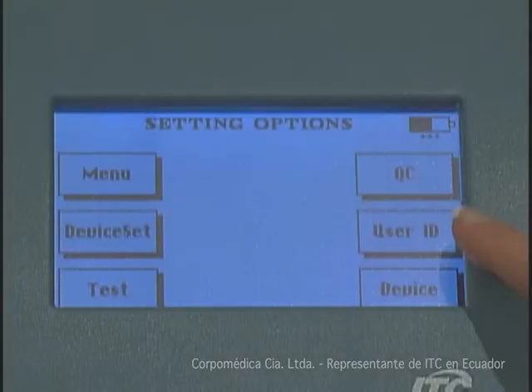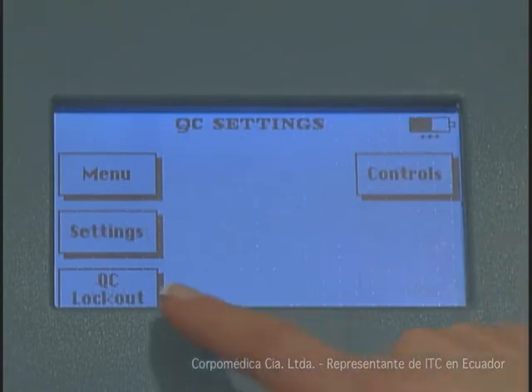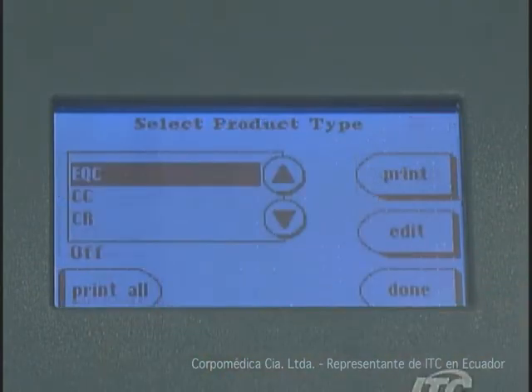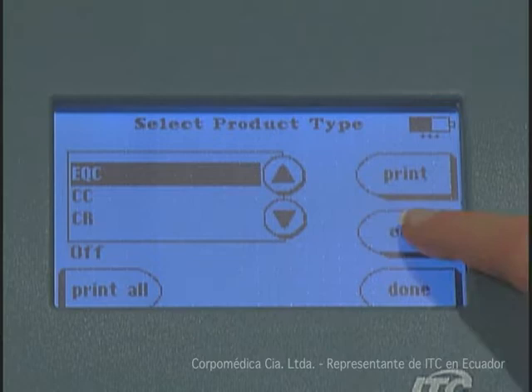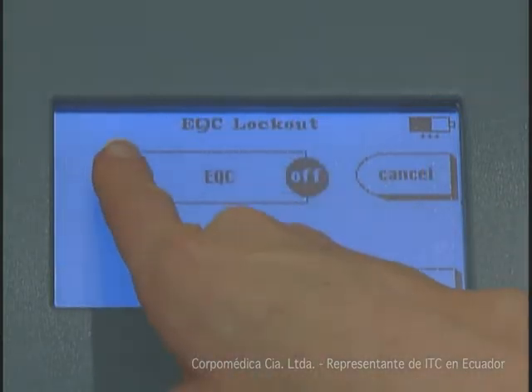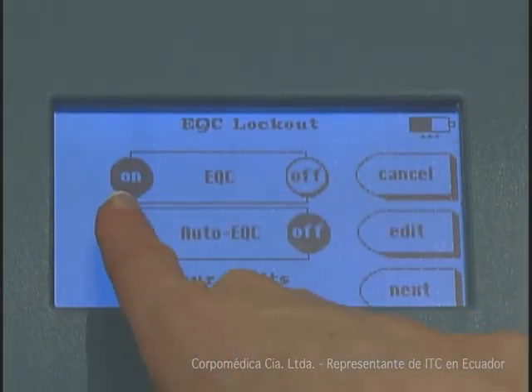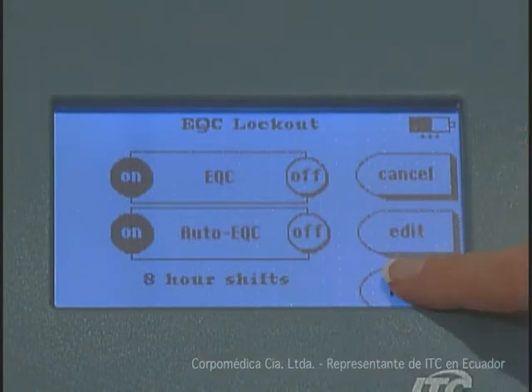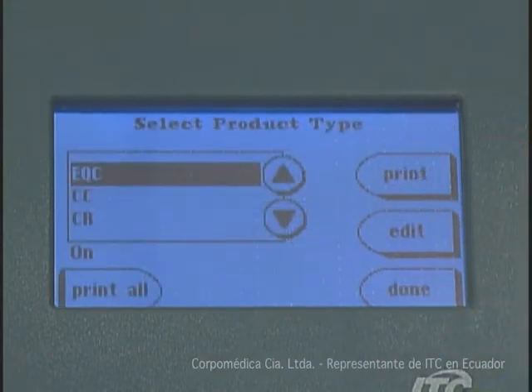QC lockout prevents a patient test from being run if quality control has not been performed within a pre-established time frame. To activate QC lockout, press QC lockout from the QC settings menu. The Select Product Type screen will display a product type pick list. Highlight the desired product type to activate or deactivate QC lockout and press Edit. Press On to activate or Off to deactivate. Press Next and then press Done. The Analyte Lockout screen displays when you have selected On.